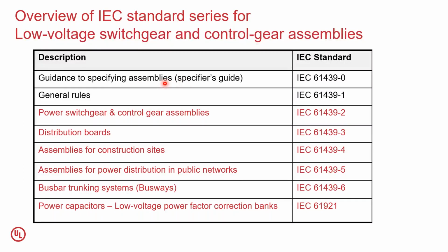Another example is the specifier might say, I want the busways to be tested at an ambient condition of 50 degrees. This is very common for the Middle East market, because the ambient condition in those regions is very high. So they use the standard, and in addition to the normal conditions of the standard, they would specify higher ambient suitability for those products. The second most important standard in this series is the 61439-1, which is essentially the general rules.